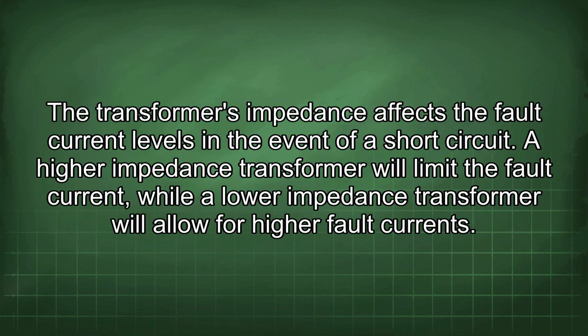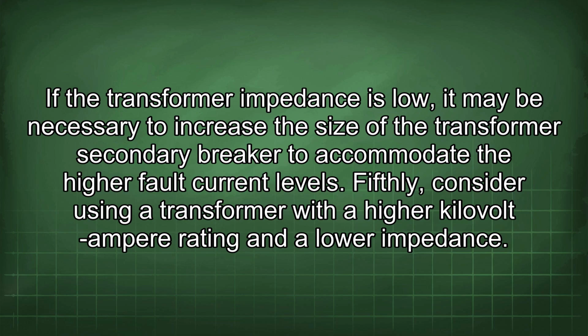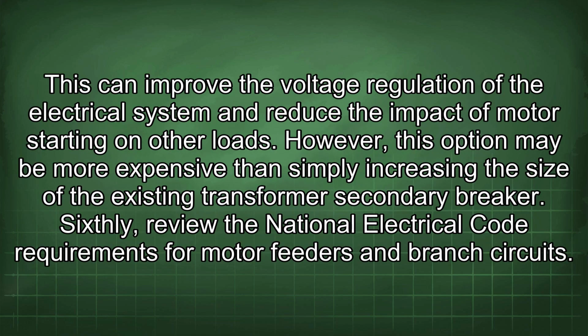The transformer's impedance affects the fault current levels in the event of a short circuit. A higher impedance transformer will limit the fault current, while a lower impedance transformer will allow for higher fault currents. If the transformer impedance is low, it may be necessary to increase the size of the transformer secondary breaker to accommodate the high fault current levels. Fifthly, consider using a transformer with a higher kilovolt ampere rating and a lower impedance. This can improve the voltage regulation of the electrical system and reduce the impact of motor starting on other loads. However, this option may be more expensive than simply increasing the size of the existing transformer secondary breaker.